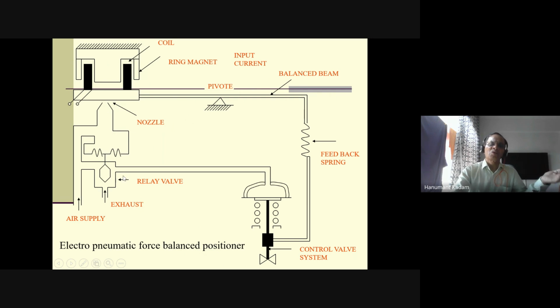See how the feedback system was developed in the pneumatic or mechanical system. Air supply is coming here into this valve, which is basically a pneumatic relay. Here 20 psi is coming, then it is a relay valve. Based on the input current, 4 to 20 milliamp, a magnetic field is generated, and the gap changes, and feedback pressure is generated. Through the relay it forces here. This is a feedback spring, and the valve gets back to its original position with the help of the feedback spring. So this is how the control valve stem works with the electro-pneumatic force balance positioner.